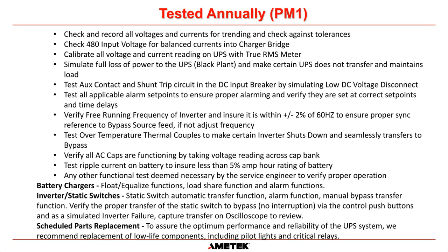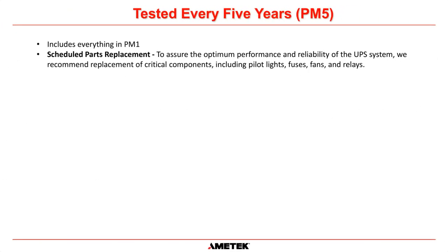And then for the annual PM, we will replace some parts, and that could be pilot lights and critical relays. So on our older systems, especially incandescent lights, we will replace on an annual basis, and the safety critical relays that we mentioned in the slides before. And then every 5 years, we will do everything that we did in the annual PM, and then we will do the scheduled parts replacement, and we'll replace pilot lights, fuses, fans, and relays.